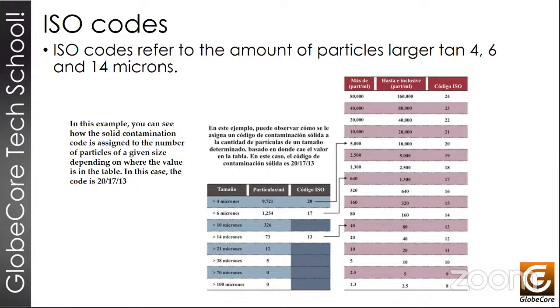Those are usually given by 3 numbers. For example, here we have an example of code of 20/17/13. The first number will always refer to the smallest particle, 4 micron particles. The second number will refer to 6 micron particles, which are kind of in between. And the third number will refer to the largest particle, and in this case, it's 14 microns. So now that we have a value of 20, 17, 13, this tells us that we must check this table to determine the minimum values and maximum values.